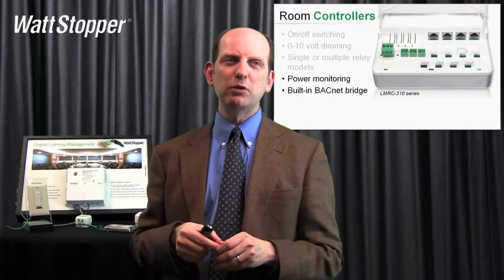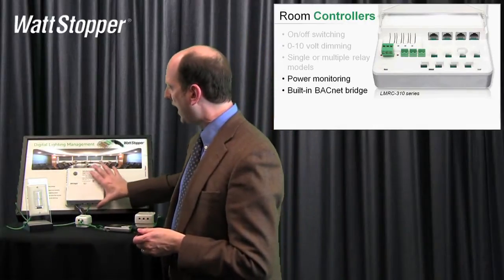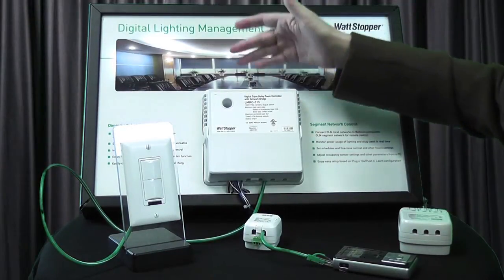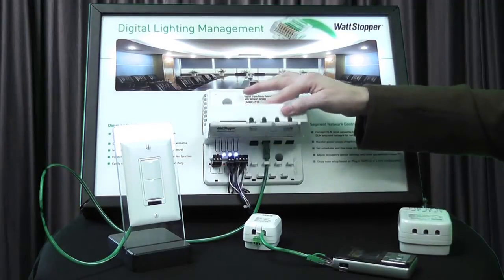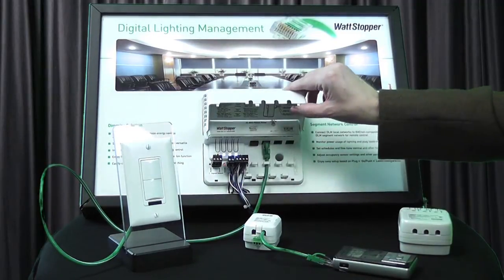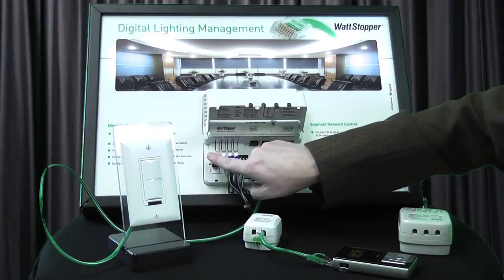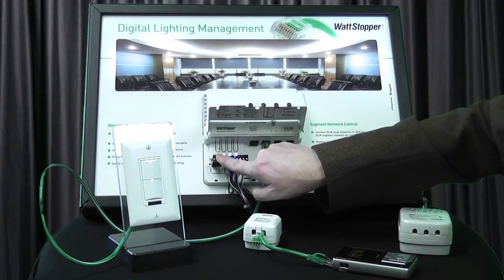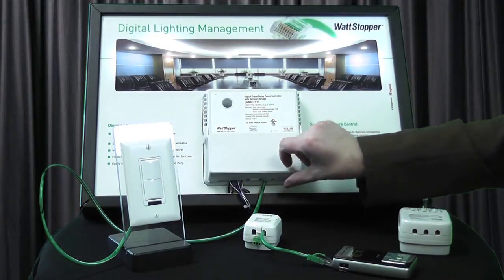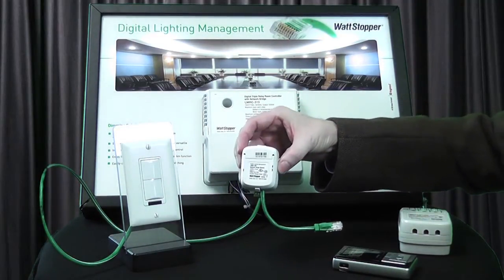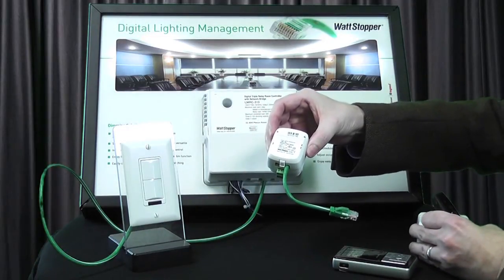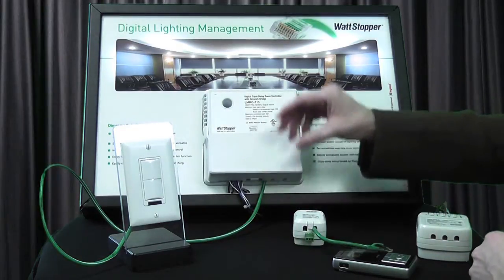Let's now talk a little bit about the room controllers. What we talked about before was that on the 300 series room controller, it's got on-off capability through its relays, it's got zero to ten volt dimming capabilities. Two things we want to point out: on the 300 series there is a network bridge that's built in, and that's what this set of terminals is for. Here's where an integrator would be able to bring their BACnet MSTP communication wire to talk to this device. There's also a separate network bridge module that would normally go with something like an LMRC 102 or a 200 series — but with the 300 series you get that built in.